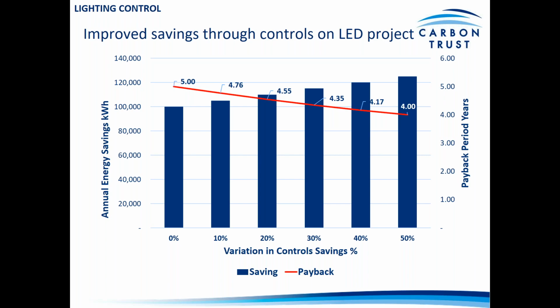Payback period without controls is 5 years, but if you're to bring in controls, that can improve dramatically. So the level of saving can be increased, and the payback can be improved. So you can see here the energy savings increasing as the controls savings increase. So as we reduce the amount of lighting operation by 10%, 20%, 30%, the level of savings increase and the payback decreases.